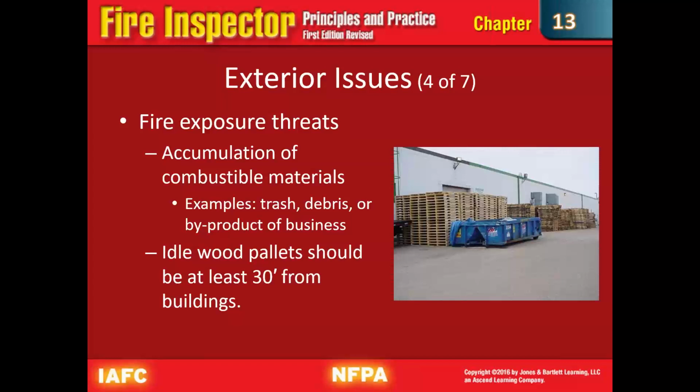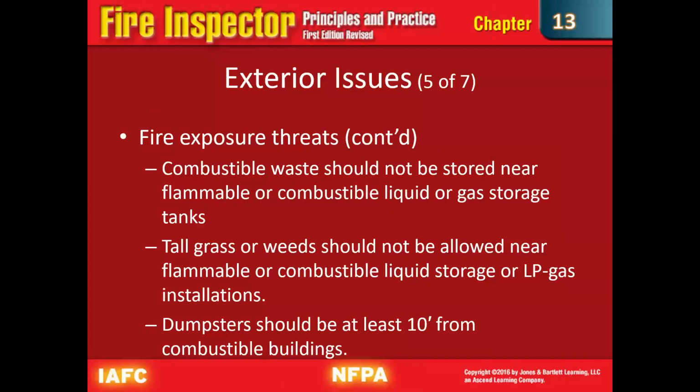Idle wood pallets should be at least 30 feet from buildings, but most of the time you're going to find them just like in that picture, stacked several high right up against the building. So be mindful of that, and it may not even be pallets. It may be something else that catches your attention that you have to get taken care of and get them to change their policy and how they store those type items.